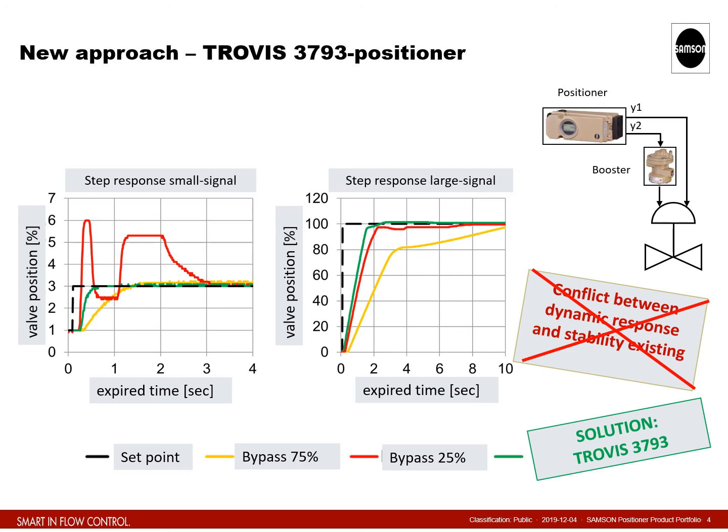In theory, you are tuning the positioner to handle small stroke movements and tuning the volume booster to handle large stroke movements. Since these are independent pneumatics, their interaction and correlation factors are much lower than the traditional solution. Thus, you will notice both green lines provide optimal dynamic response with quick rise to set point, no overshoot, and minimal steady state error.